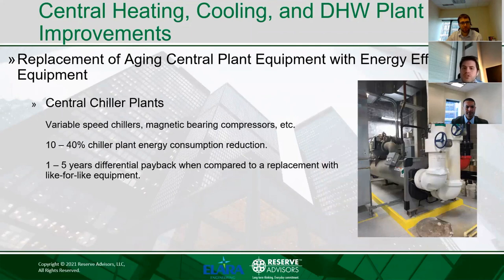So moving to central cooling plants, chiller plants. Like central heating plants, central chiller plants produce chilled water for space cooling instead of hot water. And central chiller plants in residential high-rise buildings typically consist of water-cooled or air-cooled chillers. If there's a water-cooled chiller, that means a cooling tower is also required to provide heat rejection for the water-cooled chiller system. Air-cooled chillers, those systems do not require cooling towers as they directly reject heat to the atmosphere.